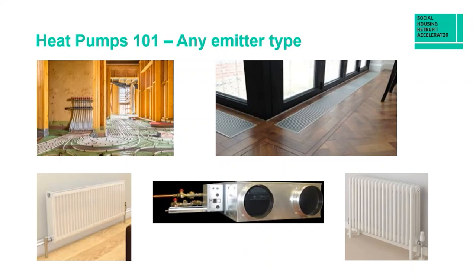Now into the myth-busting. You may have heard that heat pumps must use underfloor heating or massive radiators — not a bit of it. Underfloor heating is great because it is designed for lower flow temperatures, so it's certainly an advantage, but it's not a necessity. We can work with underfloor heating, trench heaters, standard panel radiators — K1, K2, K3s — cast iron sectional radiators, even original cast iron radiators. Fan coils work too. The key is correct sizing of all these devices for the flow temperatures needed to deliver thermal energy to any given room.